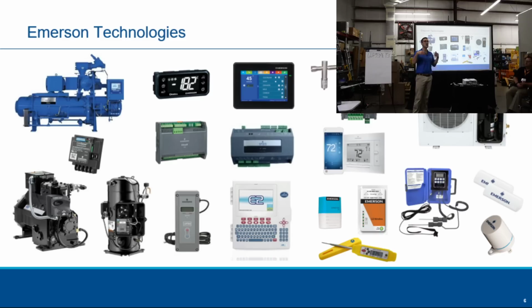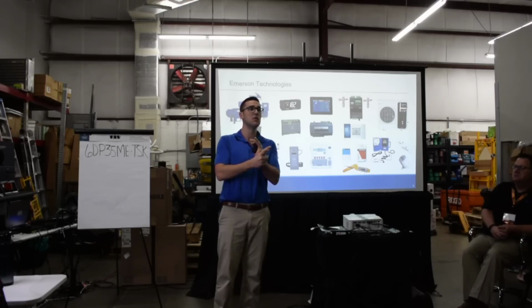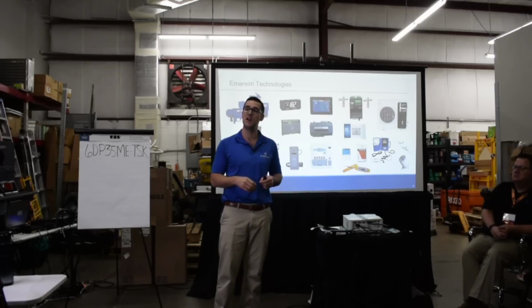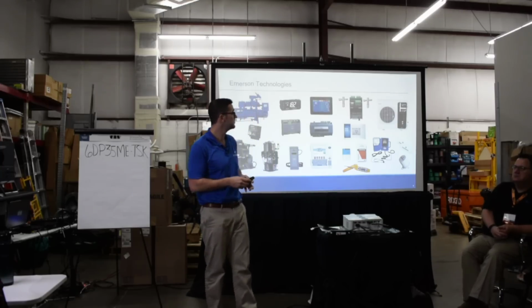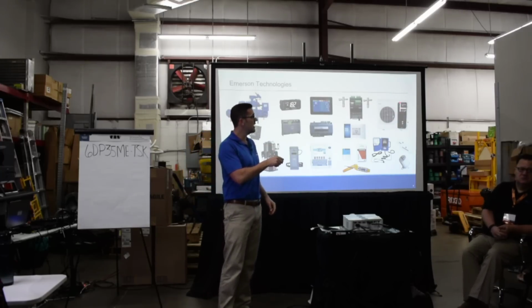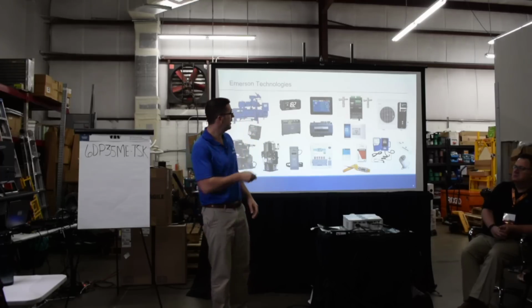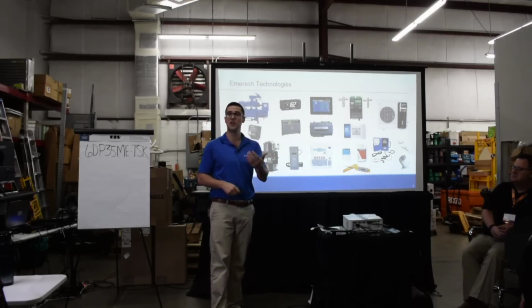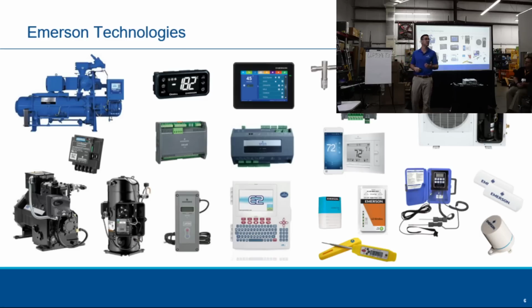So if you're off site and you get an alarm, you can go back and look at all the different alarms. Was it flood back? Was it low voltage? Was it over current? It has a really cool controller in there, a new advanced controller that will connect to one of these so you can remotely look into all your condensing units in your facility and see how they're running.